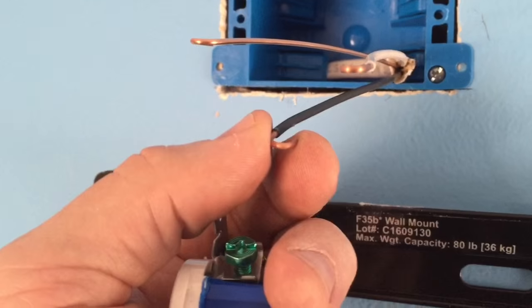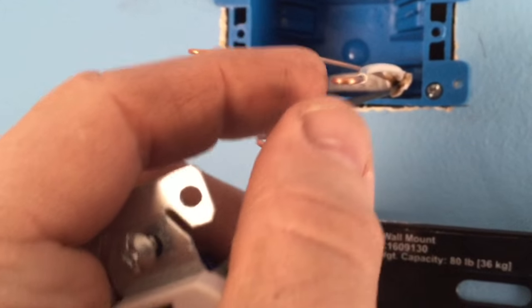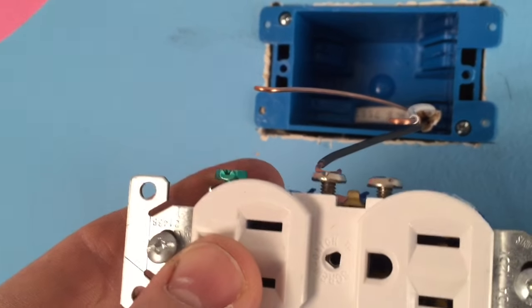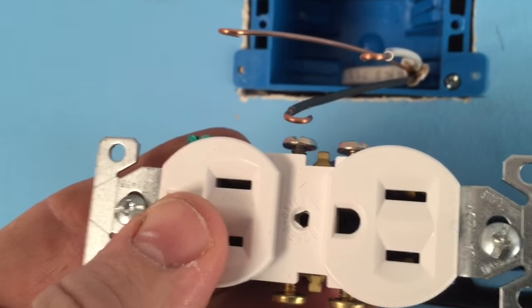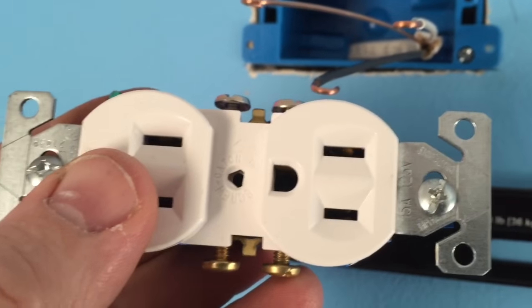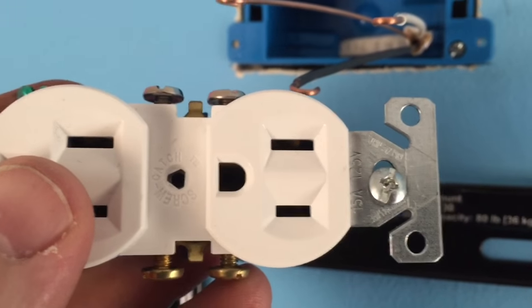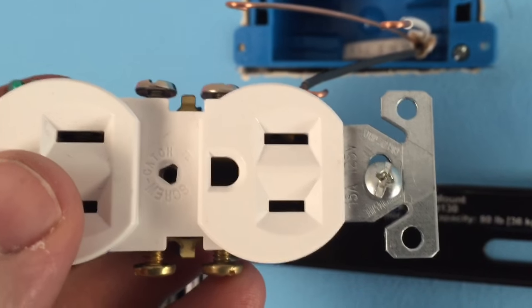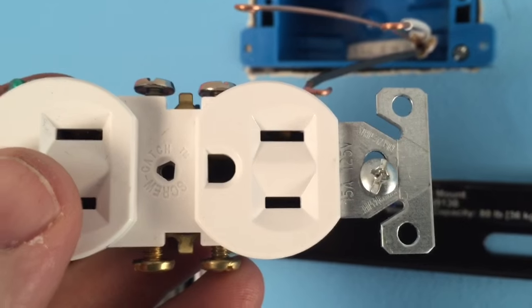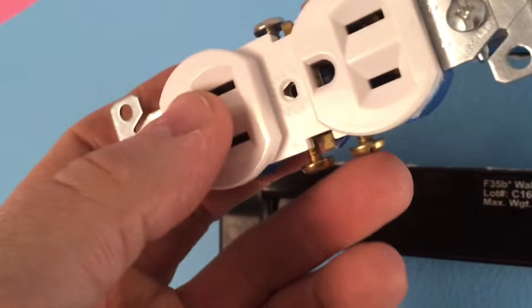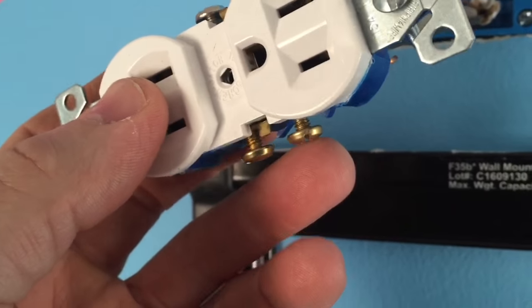Notice that we hooked the black wire this way and the white wire this way, because we're going to put it right up here like this, and we want it to go in the direction that the screw will hold it down. Now, your bigger slot on your outlet, okay, that's always your neutral. The littler slot is always the hot wire, the black wire. So the black wire will be attached on this side with the little slot.